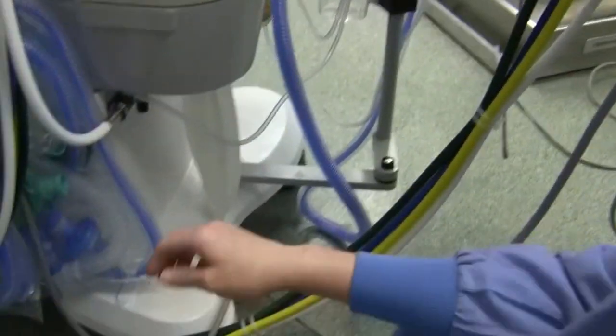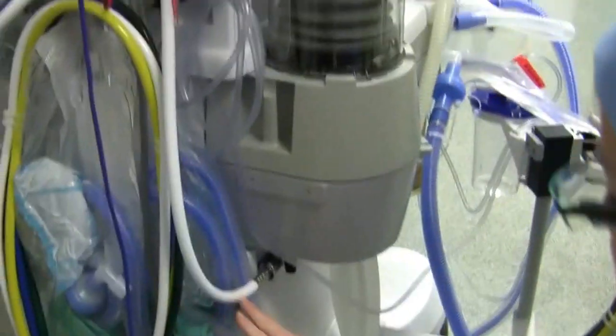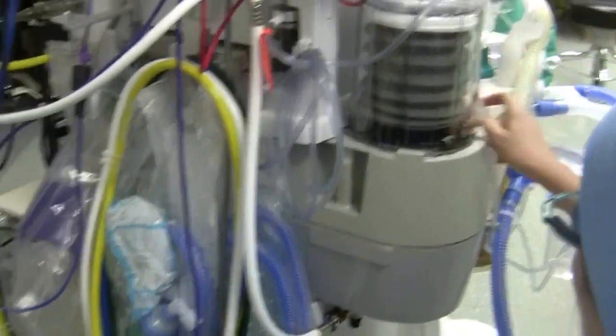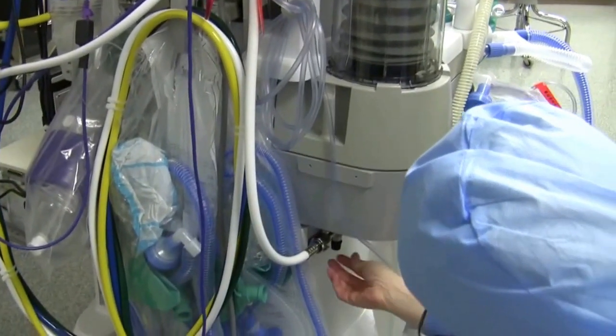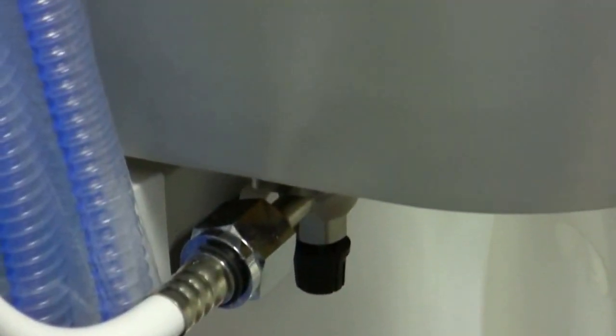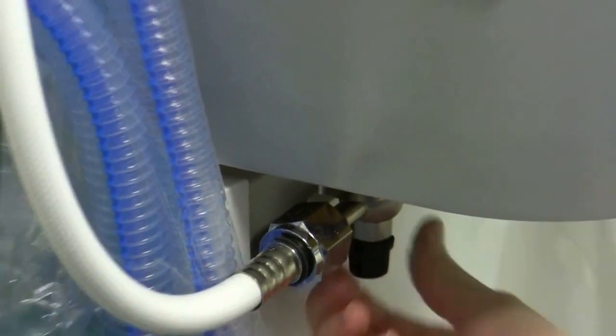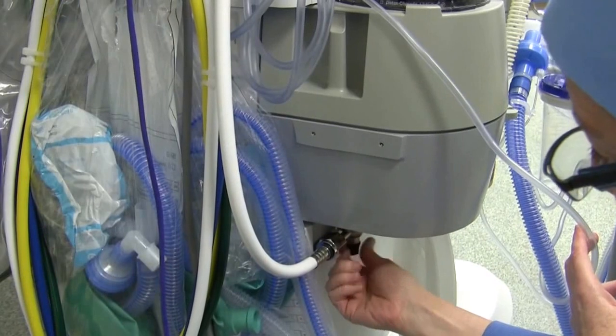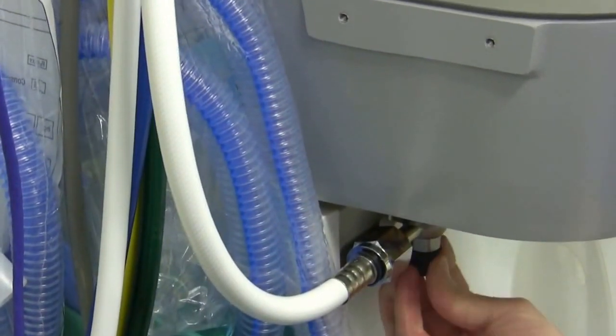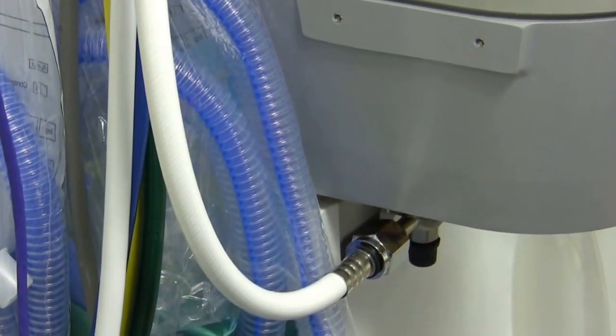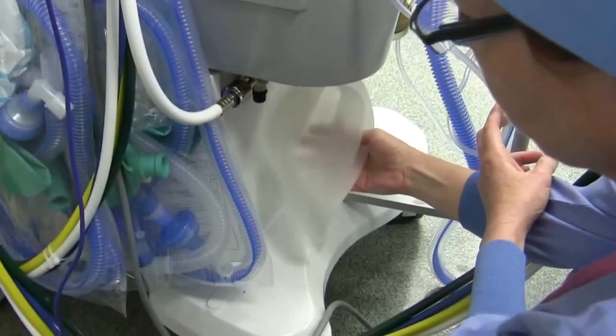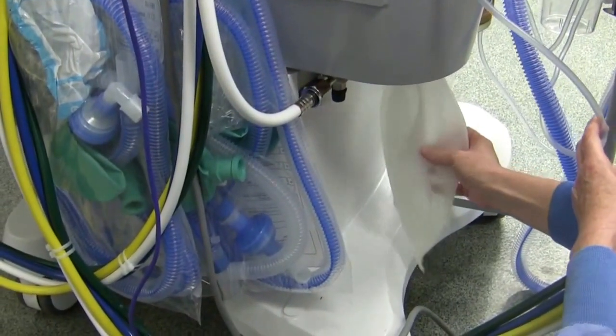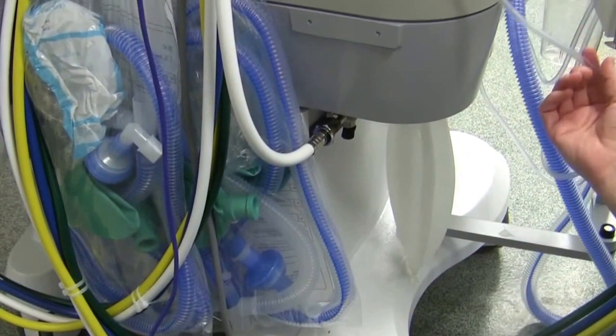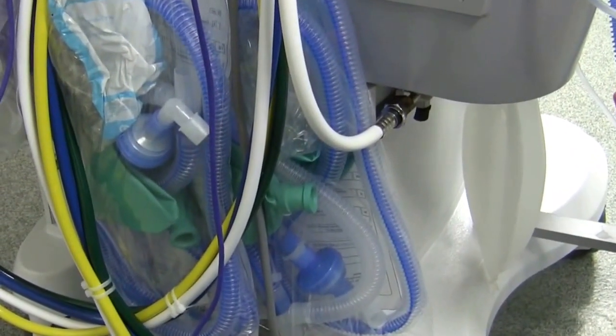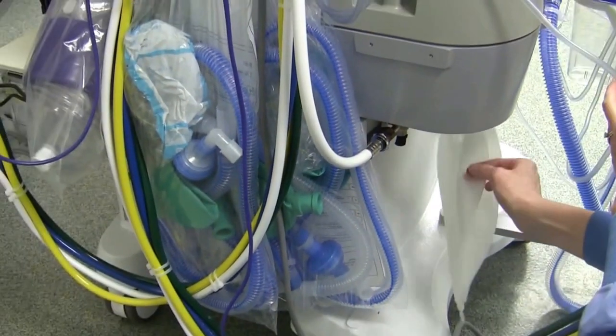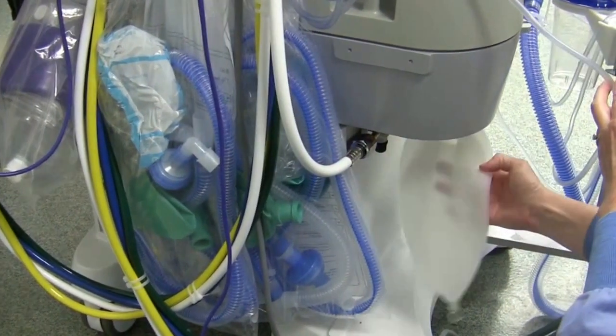The scavenging system on this machine is a passive one. It's connected to our vacuum. And where people have been a bit confused is you control it by turning this black knob. Righty-tighty, lefty-loosey, we want to have it so that it's not completely closed and about 3/4 to a full turn open. This is the bag that should be flexible but not full or taut, but there should be a little air in it. If you find that your vent is alarming high peak inspiratory pressures, it has been because this has been completely closed and this has filled up.